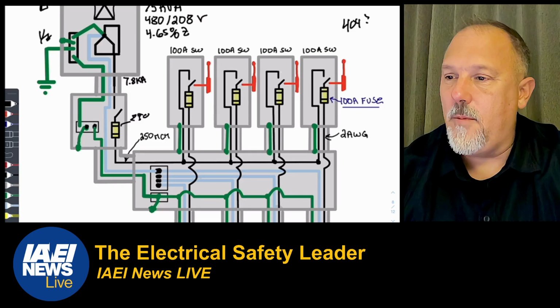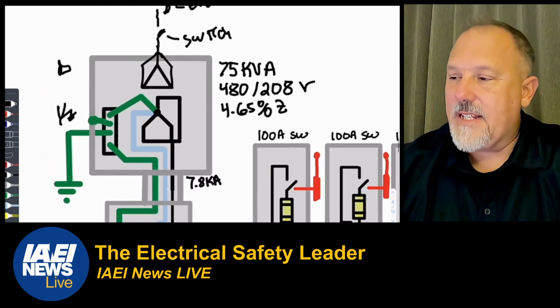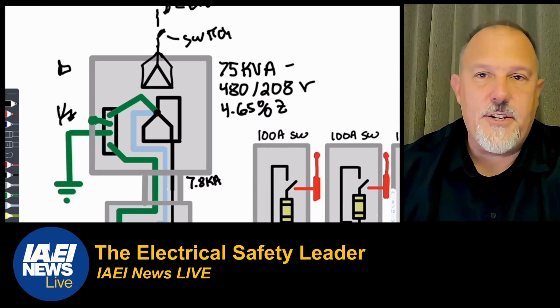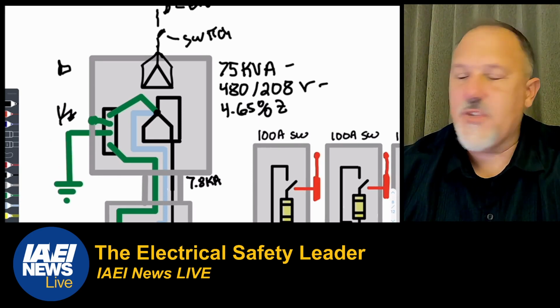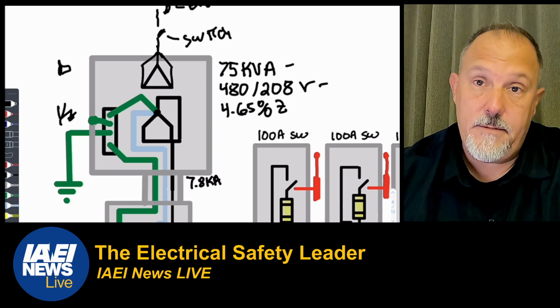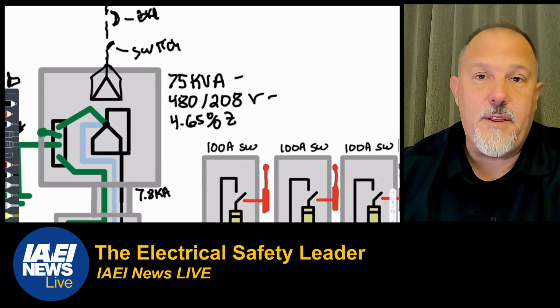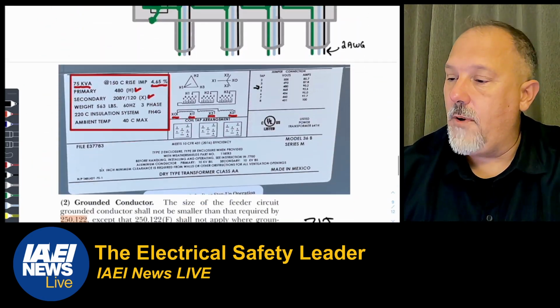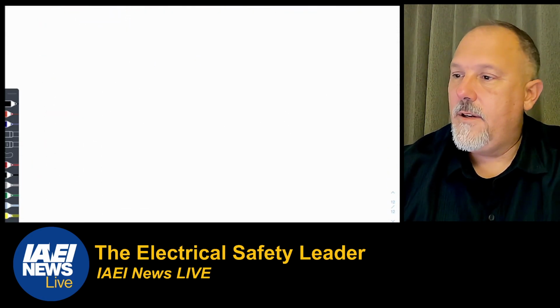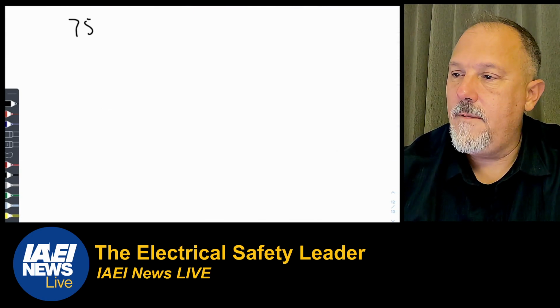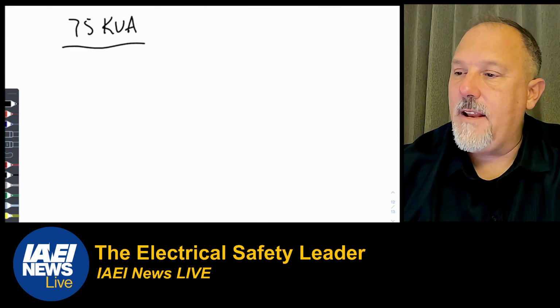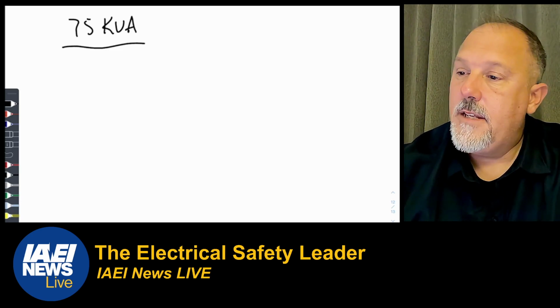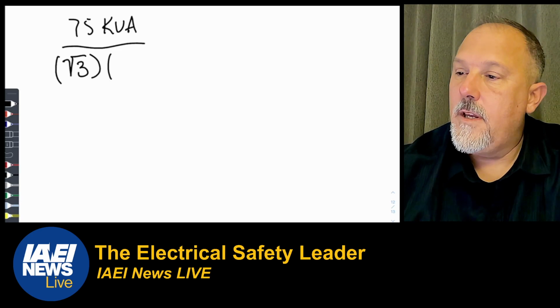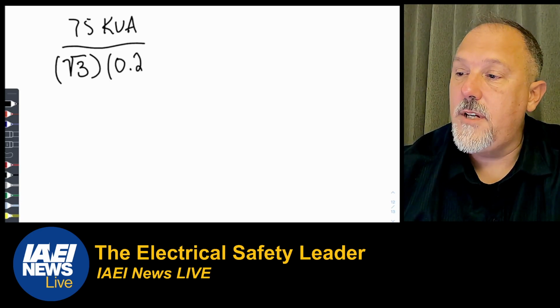So you have this transformer, right? We've got a 75 kVA transformer. We have 480 to 208 volts. We have 4.65% impedance. Now we can do a lot with that. I can calculate the full load amps on the primary and the full load amps on the secondary. Let's do that. 75 kVA divided by, we'll do the secondary first, divided by the square root of 3, divided by the kV on the secondary, 0.208, equals what? Get your calculators out.